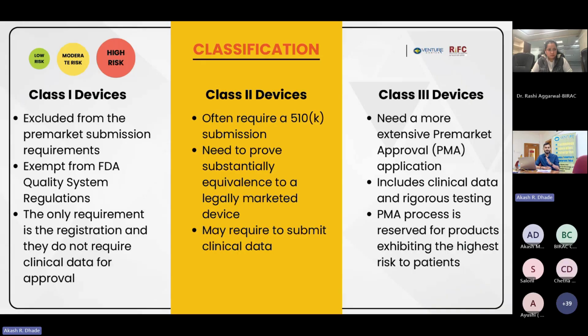If your device is similar to or better than the predicate device, then the FDA accepts your claim and you can sell that device in the US. But to do that, you need to obtain certain data. You need to prove substantial equivalence through your performance data and clinical data. So you create that documentation, you compare through a tabular format, and you submit that documentation with an approval request.